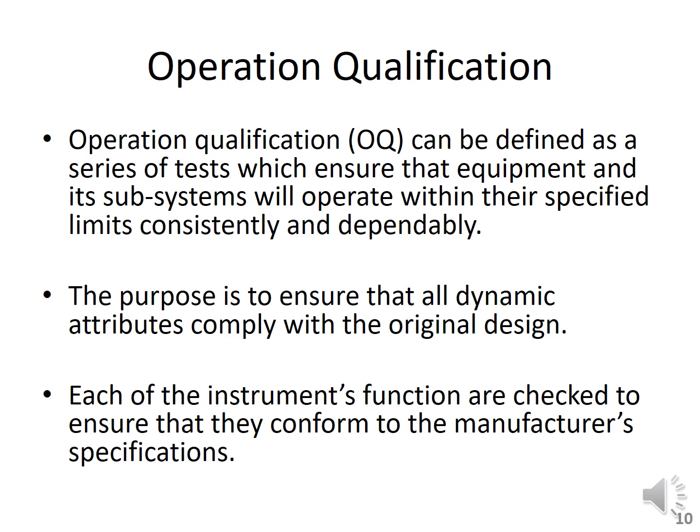Depending upon your needs and the complexity of the system, operational qualification can be combined with the installation qualification, or even the performance qualification, which is the next one, right? So operational qualification can be paired up with the previous qualification and with the upcoming qualification, just for making things smoother and making the system work more nicely.